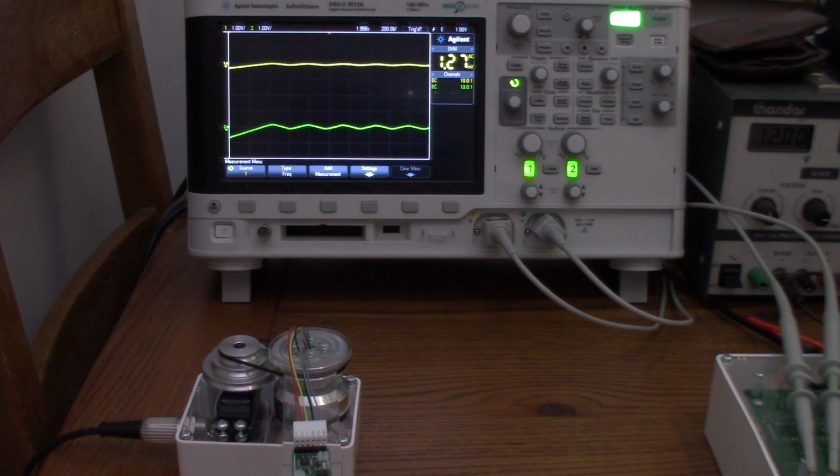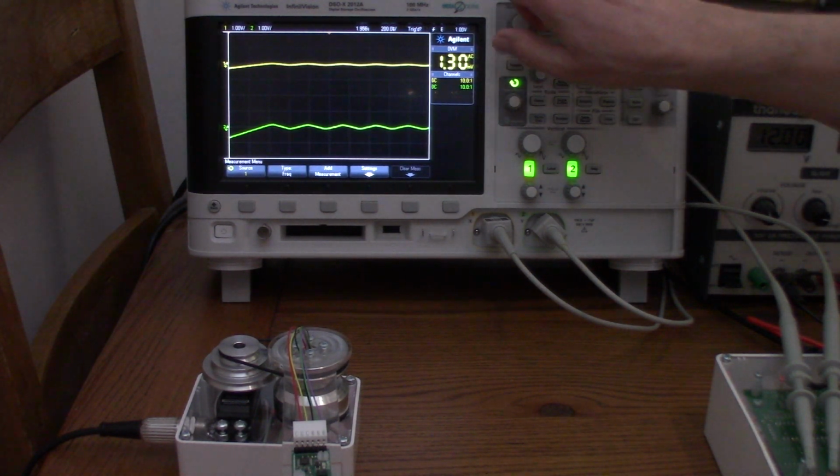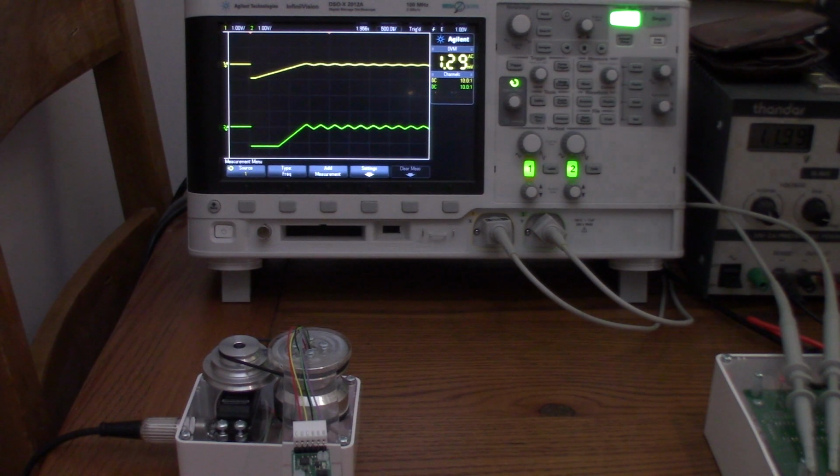So what this is saying is that we've changed the speed of response because of the pulleys by a factor of 2, so it's slower. So your K value has to increase, but interestingly enough, the actual oscillation, the integration time, hasn't actually changed a great deal, which is fascinating. So that's worth noting. So let's just put this back as it was here.